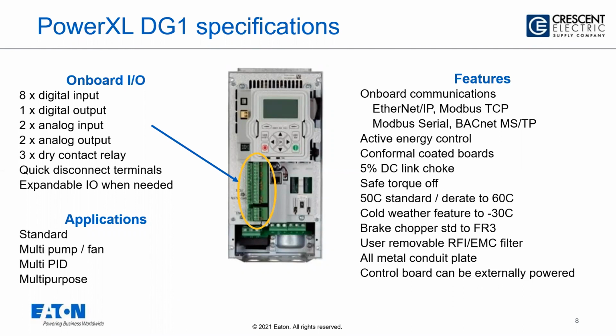This is a really nice feature if you're going to take a NEMA 3R, especially up here in the north, where you're going to have something that's going to be outdoors or on a roof. So now we can guarantee that the drive will start down to -30 centigrade. It can actually go lower, but we'll guarantee a start down that low.